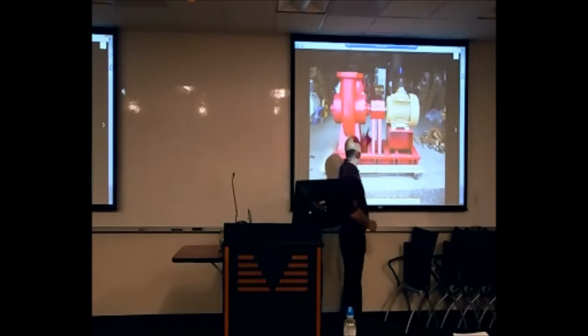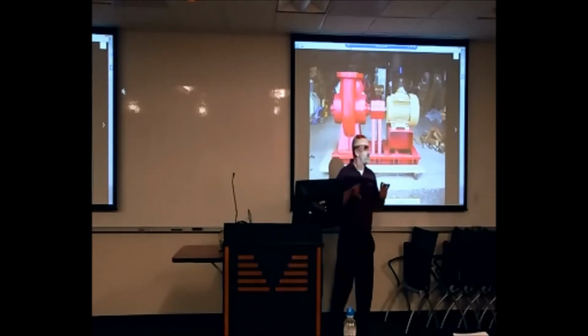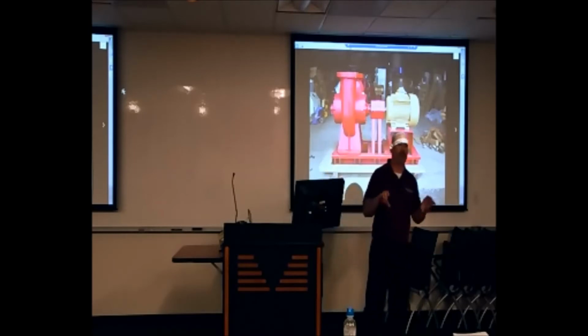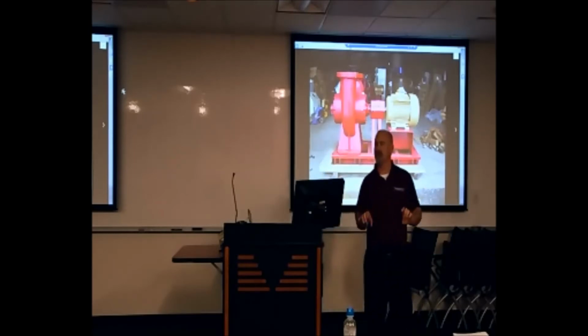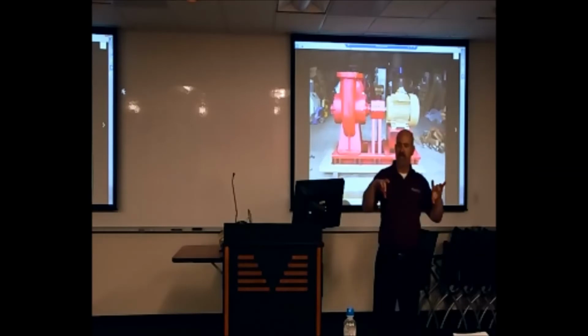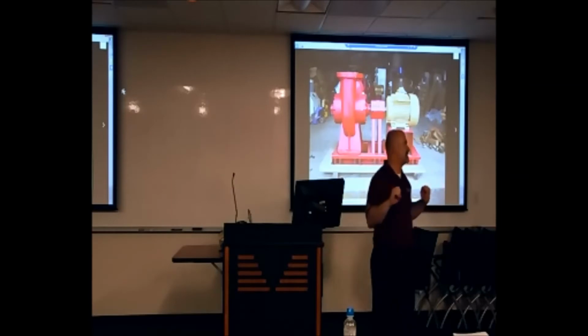Inside of both shafts, when you remove that coupler, what looks to be a stupid piece of rubber is probably the biggest thing that you need to make sure is there. It looks like a washer. It sits on the shafts going into the motor and into the pump. It's called a water slinger. And if you don't have that water slinger there, guess what happens to the water? It runs on the shaft right into your bearings. So without that there, you're going to lose your bearings, especially in an outdoor pump application, within a month.